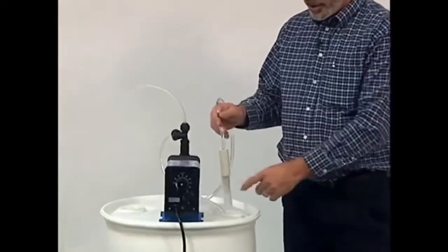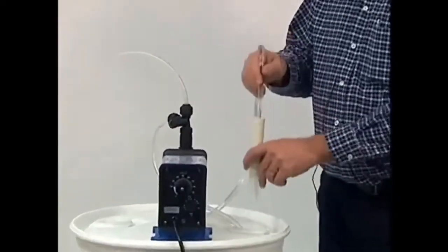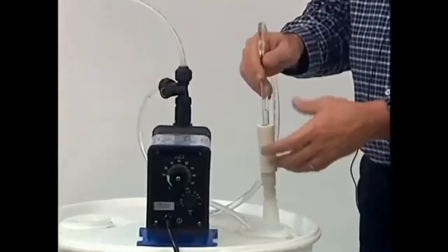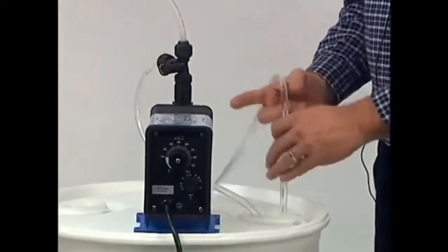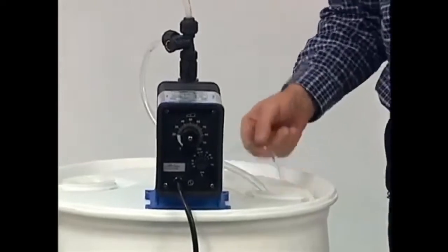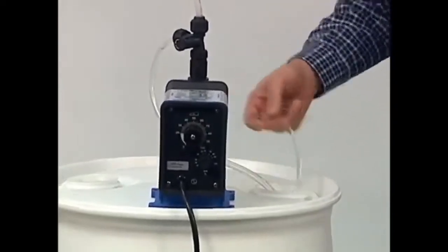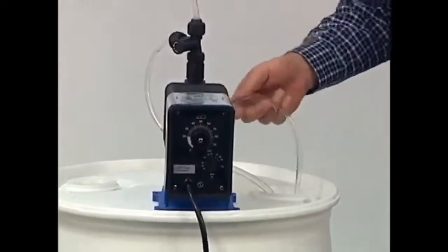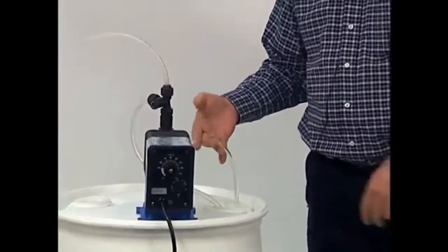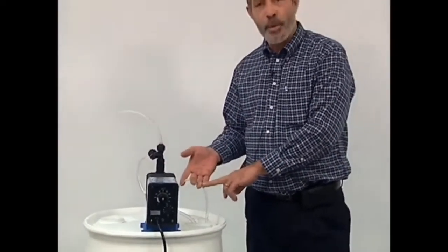If your priming valve will not allow you to prime the pump, a secondary method would be to take your suction line with the foot valve on it and jog it up and down. Your foot valve has a ball seat in it so that each time you move it up and down in the liquid, it forces chemical into this line, holding it here, making it easier for the pump to prime.